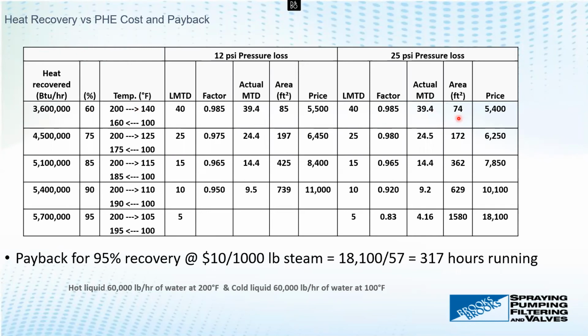If you go through all this, the last one is the 95% regeneration, where you are able to heat the cold side water from 100 to 195 degrees Fahrenheit. The cost of the heat exchanger is 18,100. But if you calculate the payback period for this 95% heat recovery, assuming $10 per 1,000 pounds of saturated steam, though that number may be different, and I'm just saying this for calculation purposes, you will recover this 18,100 divided by 57 in 317 hours of running this exchanger.